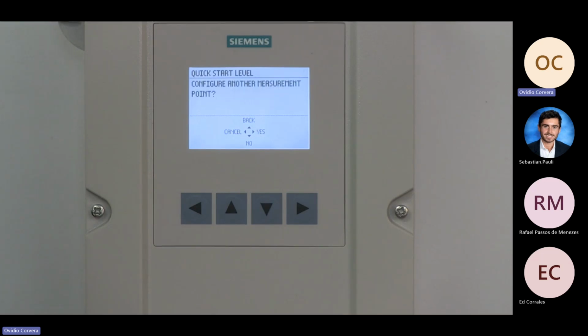Congratulations, you have successfully configured the measurement point 1. If this is a dual point unit, you can configure the next point using the right arrow to select Yes. If this is your only point of measurement, then finish the configuration using the down arrow to select No. If you need to make any changes, use the up arrow to select Back to scroll through the wizard to ensure the information is correct. If you want to start over again, press the left arrow to select Cancel. If you are confident that you have entered all the correct data, then load and save the values into the sensor using the down arrow to select Finish.